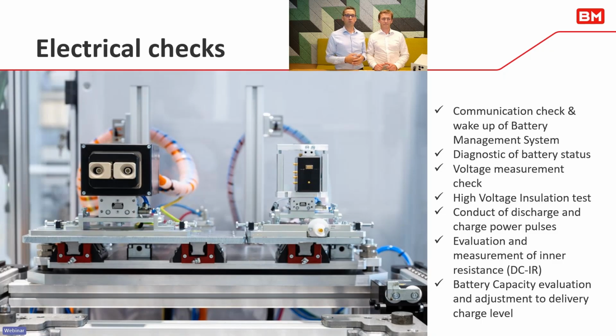The next step would be a high voltage test. This is mostly the high voltage insulation test, where we apply a voltage of up to 2000 volts DC onto the housing and the battery plus or minus pole and measure the insulation resistance, which has to be above a certain level to guarantee that there is no insulation failure, which could cause any kind of impact on the battery pack level.